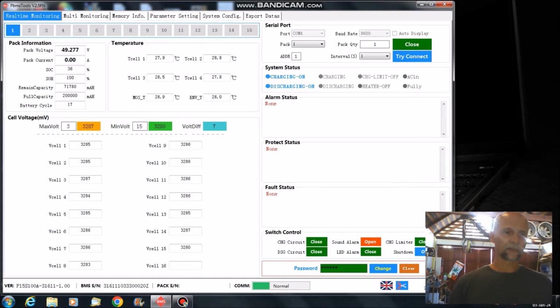Then all the cell voltages, we have maximum voltage and minimum voltage, and the differential voltage here. On the right side we have alarm status, protection status, fault status, etc. This will later show us when we are entering an alarm and when a protection state. When there's a protection state, the BMS will of course shut down the battery. When there's an alarm status, some other triggers could be set and something could change here in our battery.